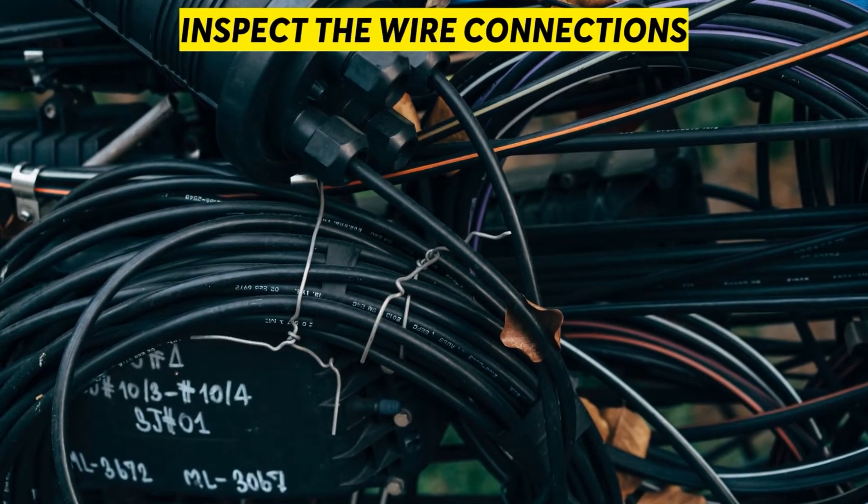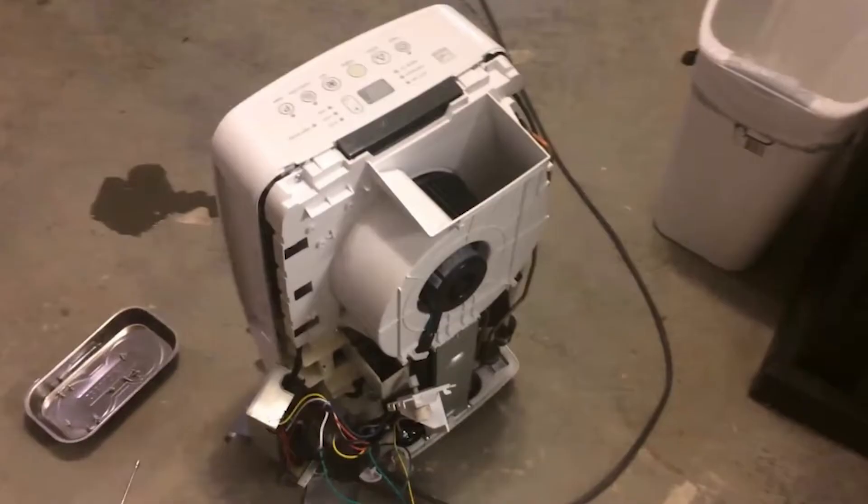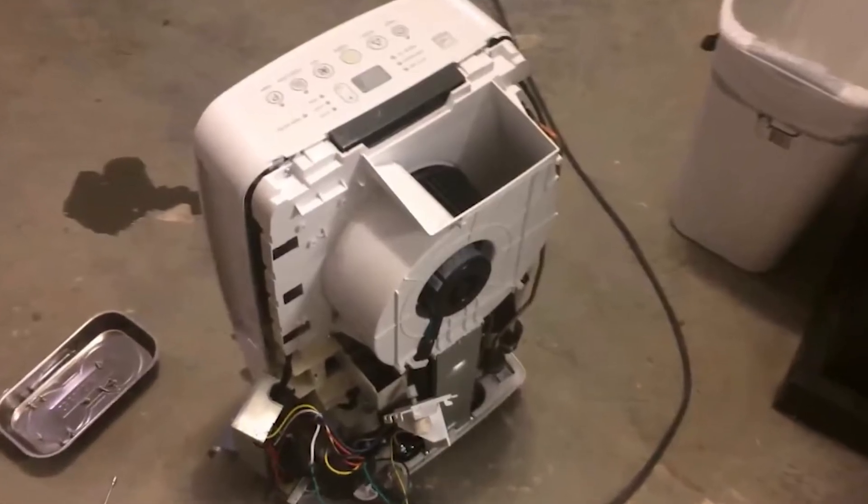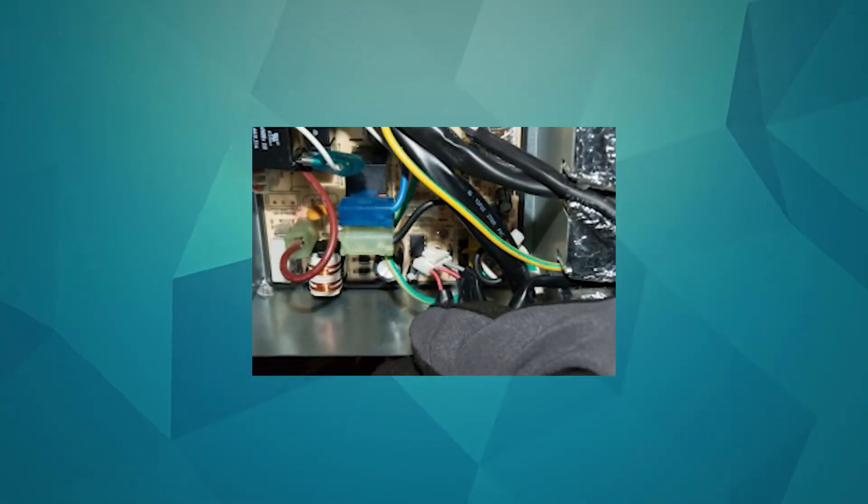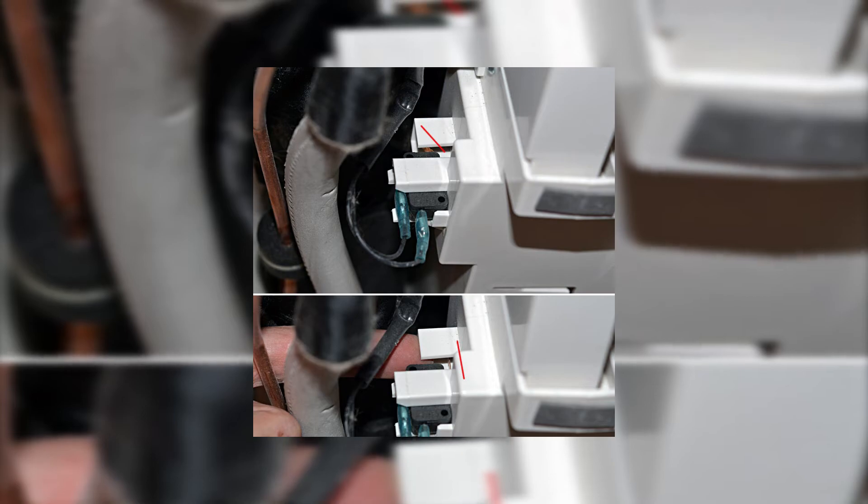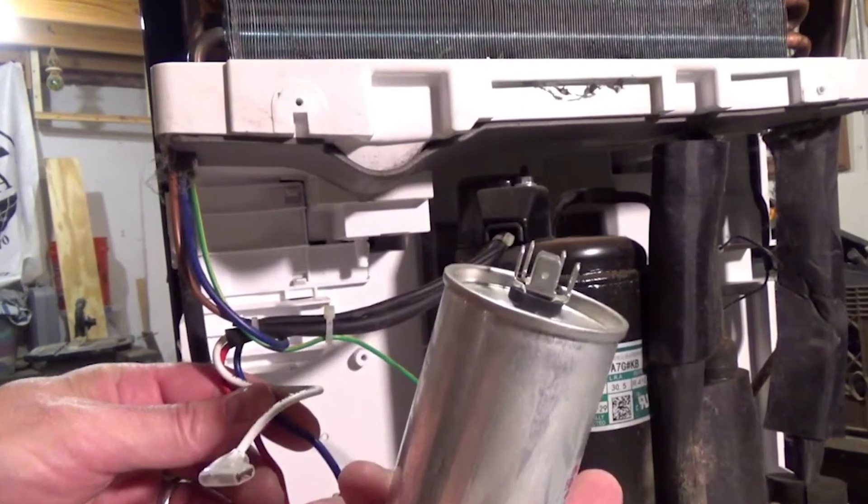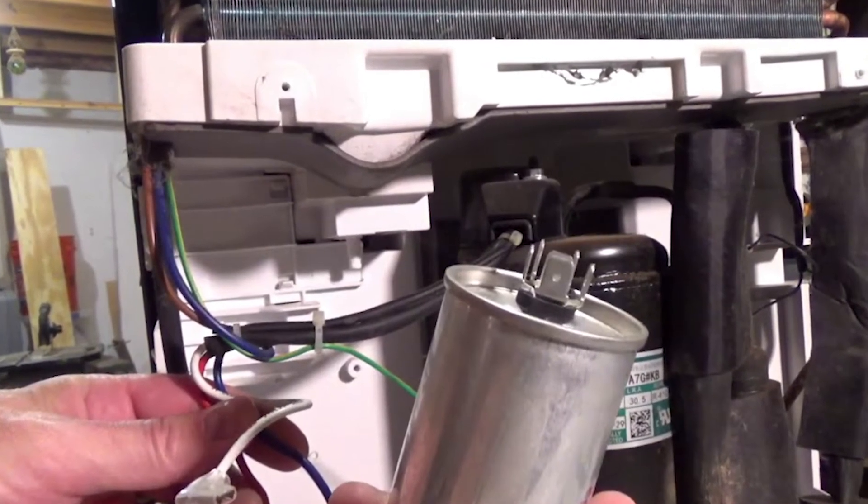Inspect the wire connections. If you find the humidity sensor is not the problem, check the wire connections. Carefully inspect each wire and ensure they are well secured. Open the terminal blocks and check the pins. If bent, it could be the cause of the malfunction. If the pins are perfect, the wire connection is not the problem.